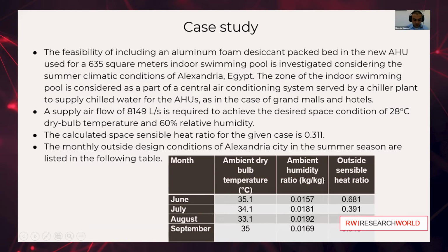The case study investigates the feasibility of using the proposed system to serve a 635 square meters indoor swimming pool located in Alexandria, Egypt. The pool is a part of a grand hotel served by a water-cooled chiller plant. The calculated supply air required for the pool is 8,149 liters per second to satisfy a 28 degrees Celsius dry bulb temperature and 60% relative humidity. The calculated space sensible heat ratio for the given case is 0.31. This is due to the high latent load resulting from the activity inside the swimming pool.